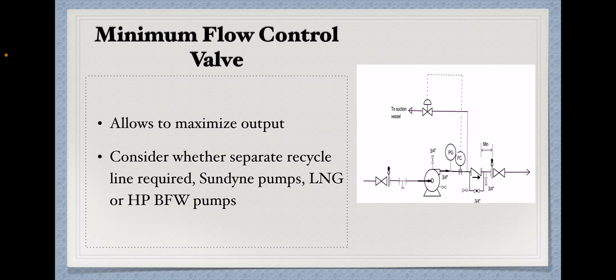So, this kind of design is provided for services where we want to maximize the forward flow. This is given in such as reaction feed flow which determines the production of the unit. So, in this case we do not want to have any recycle flow which may cause loss in production in a normal situation.